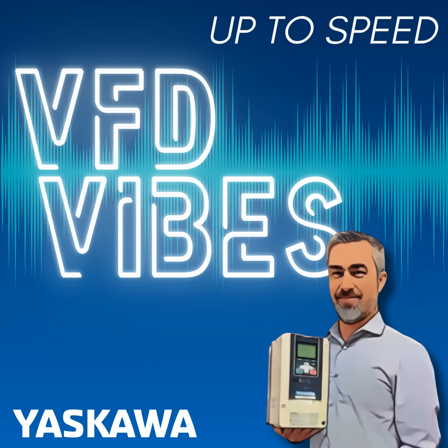And the technology operates on the principle that if you look at a balanced 3-phase power source, the voltage difference between phase 1 to phase 2 added to the voltage difference between phase 2 to phase 3 equals your total line voltage. So the drive, using very high-speed switching, takes advantage of what I will call a virtual DC bus to use to generate an output to the motor.